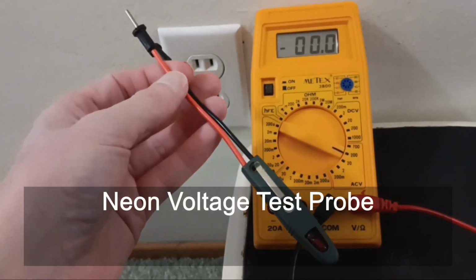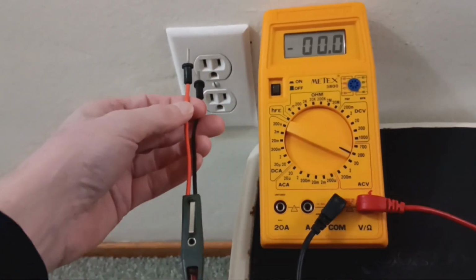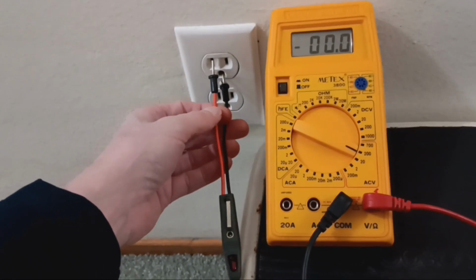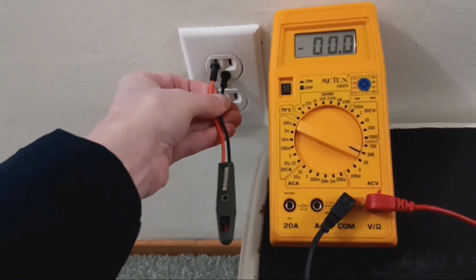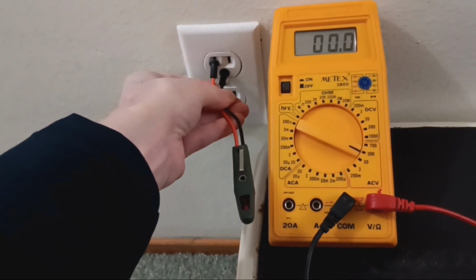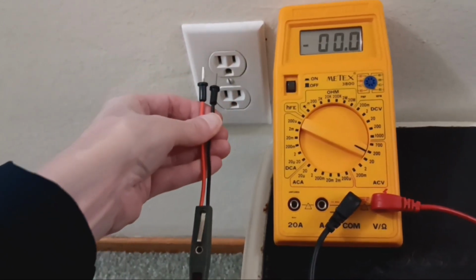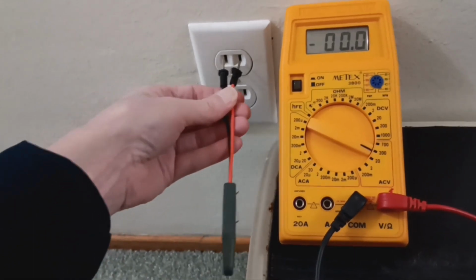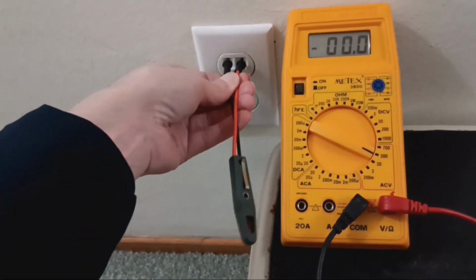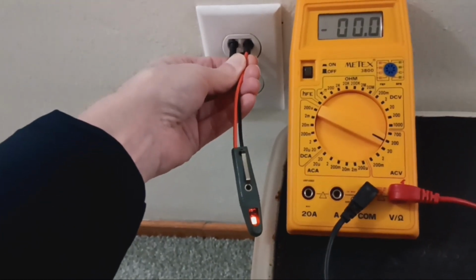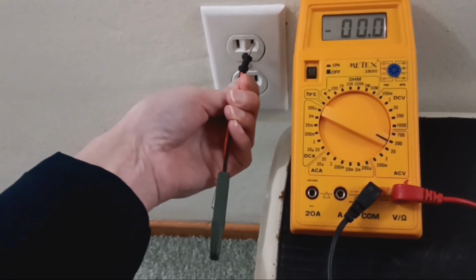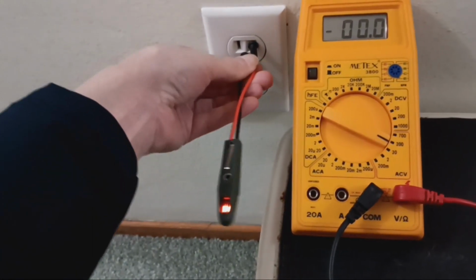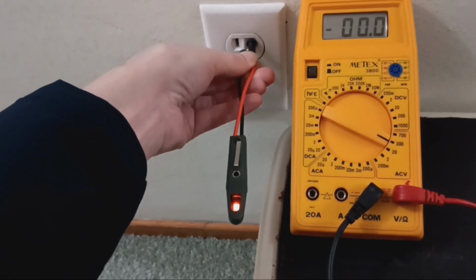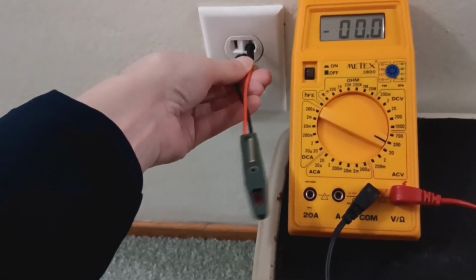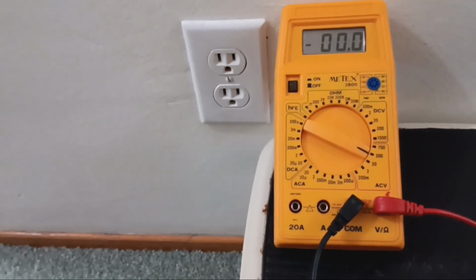Now I'm going to test with the neon voltage probe. I'm going to test from the ground to the neutral first. And that's not lighting up. Now I'm going to test from the hot to the neutral. And you can see that's lighting up. Now I'm going to test from the ground to the hot, and you can see that's lighting up. So that indicates that the outlet is wired correctly.